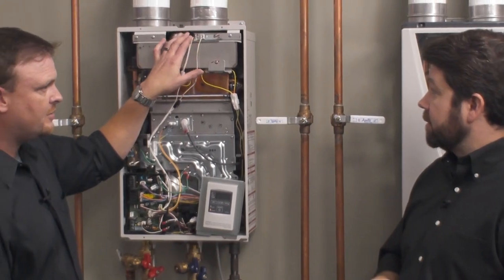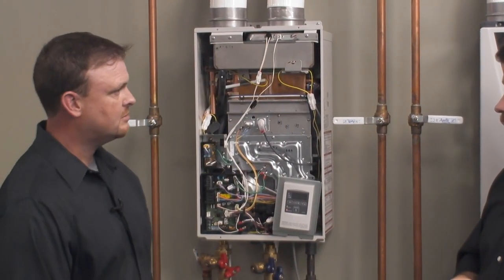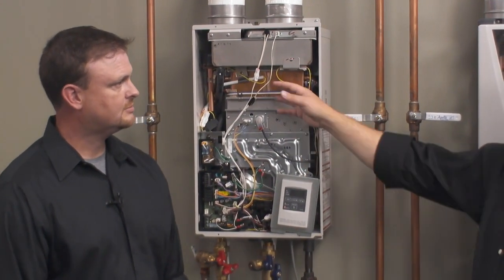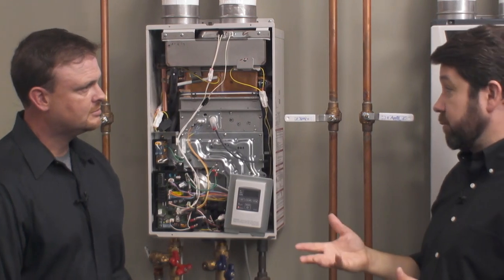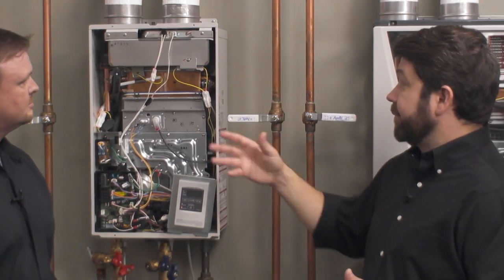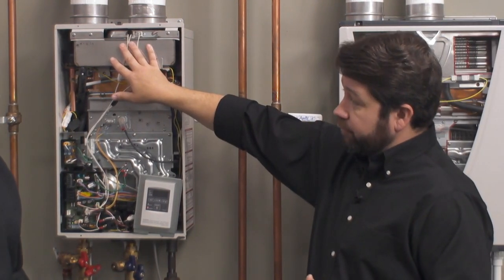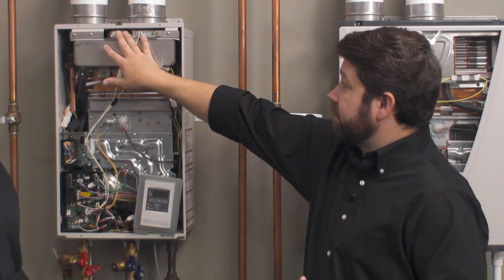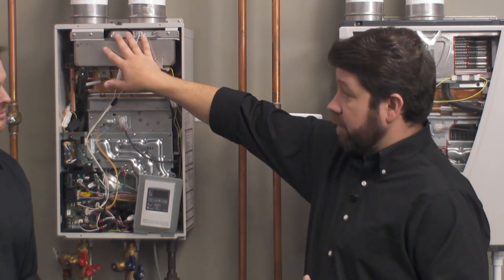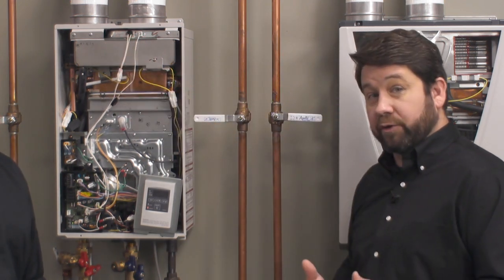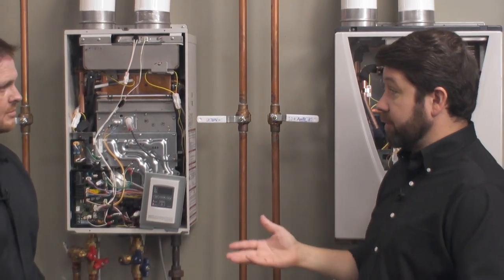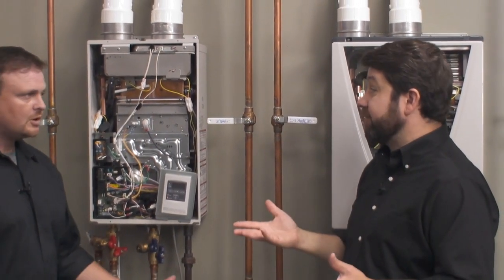Okay, and that was on the thermistor. What about the secondary? In the off chance that the thermistor, for some reason, wouldn't be accurately reading those temperatures, and we actually are increasing those flue temperatures to a dangerous level, this high limit for the exhaust will open up at 149 degrees, and it will stop operation of the water heater so we don't have an unsafe condition.